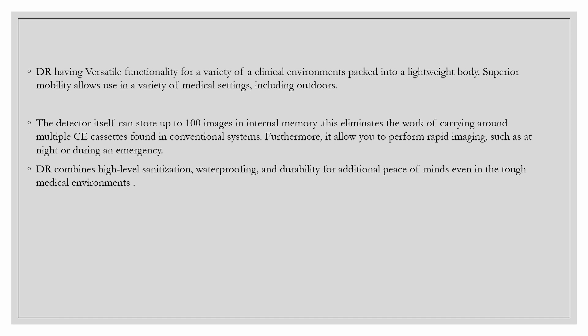DR has versatile functionality for a variety of clinical environments in a lightweight body, allowing superior mobility in various medical settings including outdoor use. The detector itself can store up to 100 images in internal memory, eliminating the need to carry multiple CR cassettes. This allows rapid image acquisition at night or during emergencies. DR panels also feature high-level sanitation, waterproofing, and durability, even in tough medical environments.